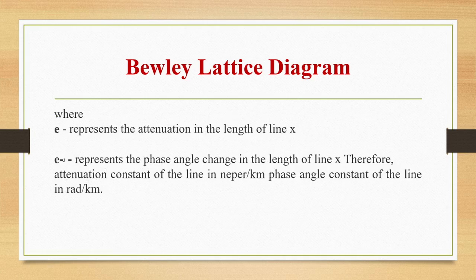If gamma is the propagation constant of the transmission line and E is the magnitude of the voltage surge at the sending end, then the magnitude and phase of the wave as it reaches any section at distance X from the sending end is given as E_X = E·e^(−αX)·e^(−jβX), where e^(−αX) represents the attenuation and e^(−jβX) represents the phase angle change over length X. Alpha is the attenuation constant in nepers per kilometer and beta is the phase angle constant in radians per kilometer.